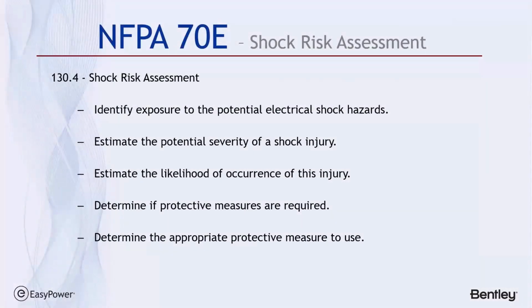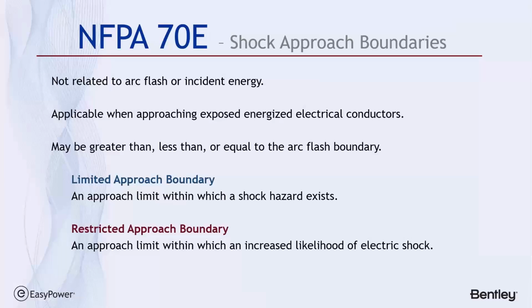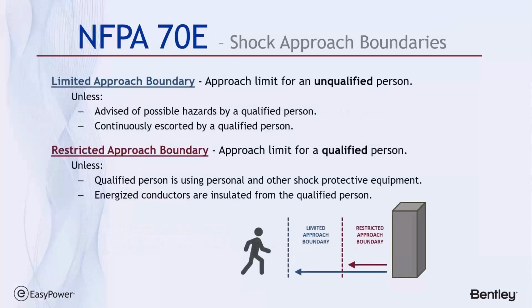So that brings us to the risk assessments themselves. The first is shock risk assessment, and its purpose is to identify exposure, estimate the potential severity, and then determine if PPE is required. It's not related to arc flash or incident energy. It's only based upon the voltage of the exposed bus and it defines two boundaries. One's a limited approach boundary and the restricted approach boundary. And graphically, the limited approach boundary is the one farthest away from the equipment, and it's defined as the approach limit for an unqualified person unless that person's advised of possible hazards by a qualified person and is continuously escorted by a qualified person. It's important to note that neither of these hazards exist when the equipment's closed and secured and there's no exposure to electrified buses.